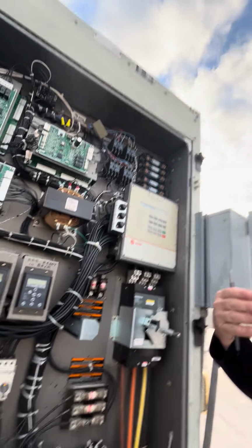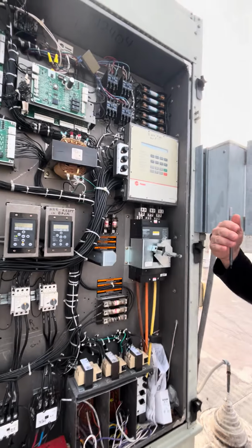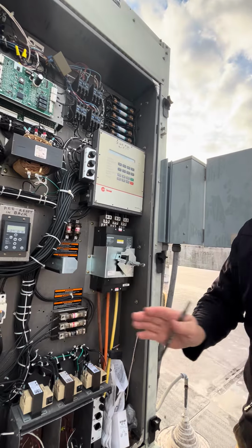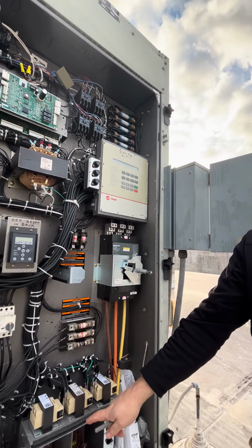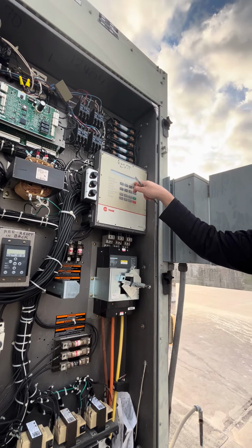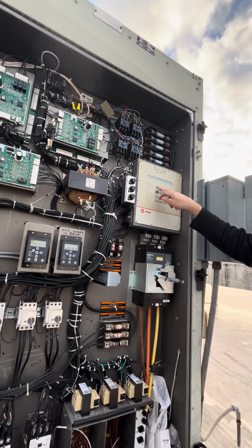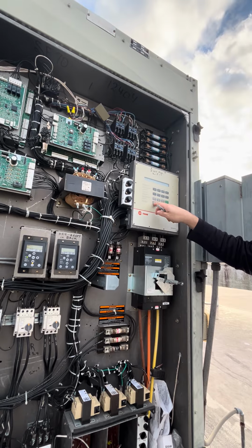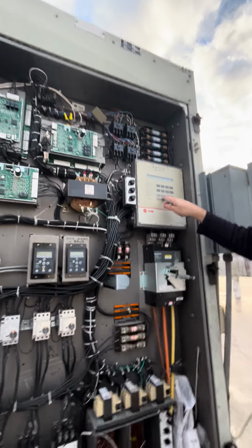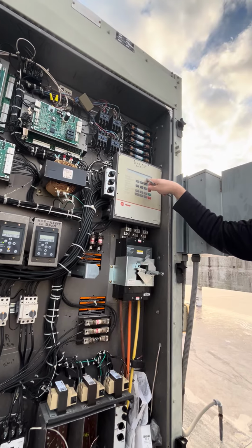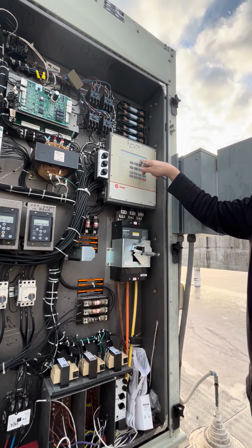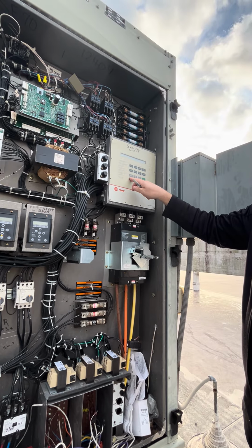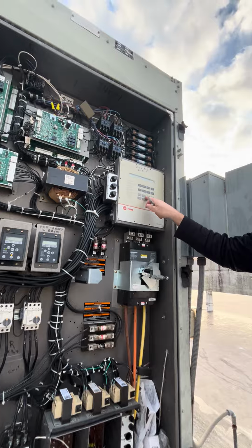So in its simplest terms, we got down to 72 degrees. We locked out the cooling, right, through that demand limit contacts. Our supply air set point is showing 75. Right now we're giving it 6.72 volts. Okay. The unit sees 6.72 volts.